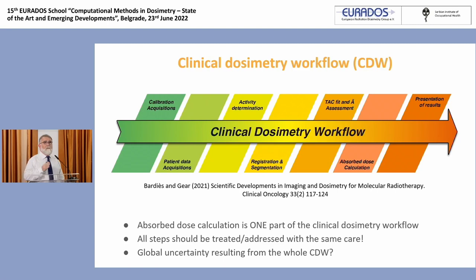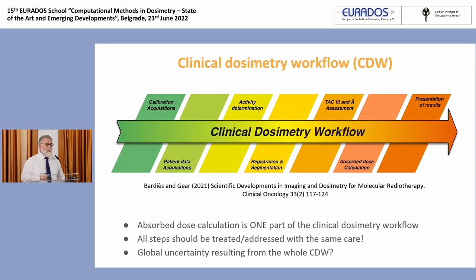When you consider all the steps, they go from the calibration of the imaging systems, acquisition of patient images, quantification, assessment of the activity present in the patient, segmentation — defining regions of interest from which you want to get the activity — then registration, because images come at different time points and the patient may not be positioned exactly the same way from one day to the next. Then, according to the MIRD formalism, integrating the time-activity curve gives you the number of decays in the volume of interest. Then you have the absorbed dose calculation.